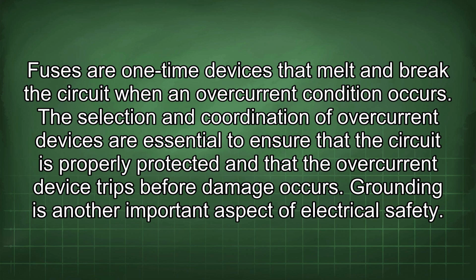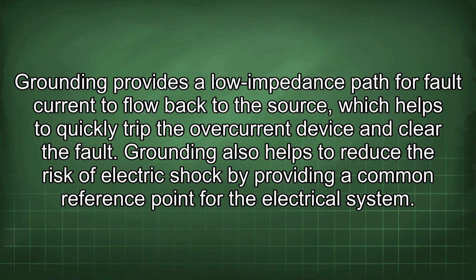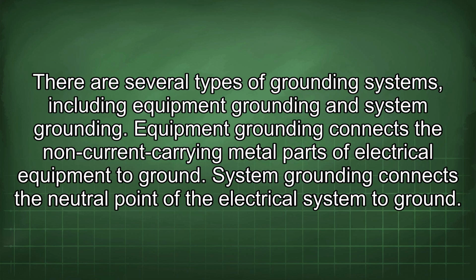Grounding is another important aspect of electrical safety. Grounding provides a low impedance path for fault current to flow back to the source, which helps to quickly trip the overcurrent device and clear the fault. Grounding also helps to reduce the risk of electric shock by providing a common reference point for the electrical system. There are several types of grounding systems, including equipment grounding and system grounding. Equipment grounding connects the non-current carrying metal parts of electrical equipment to ground. System grounding connects the neutral point of the electrical system to ground.